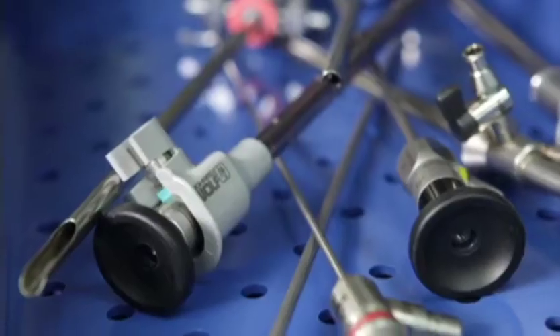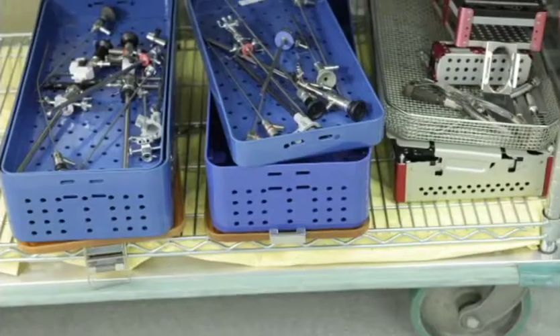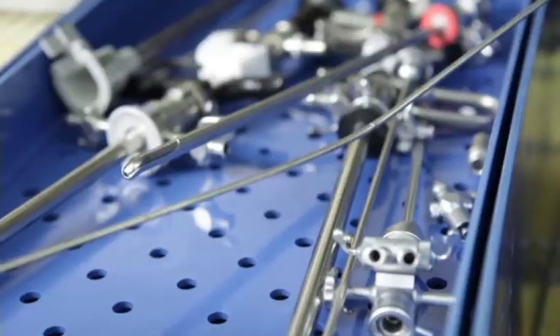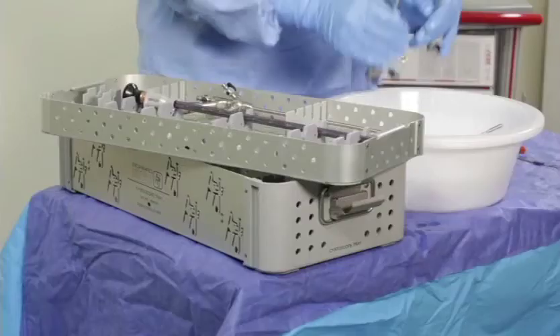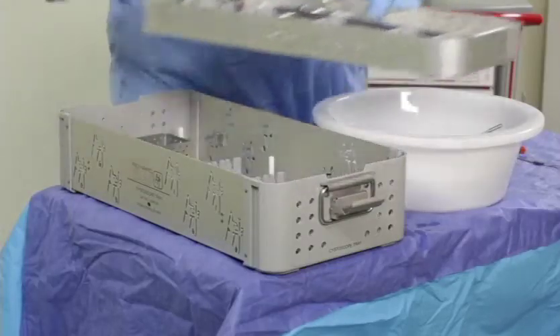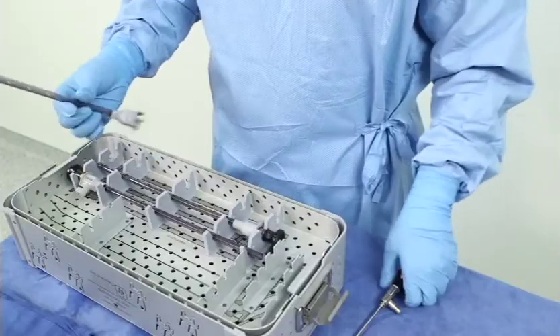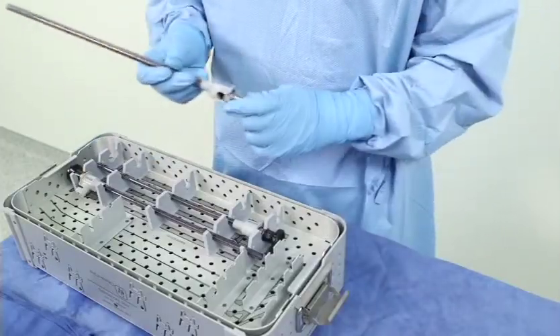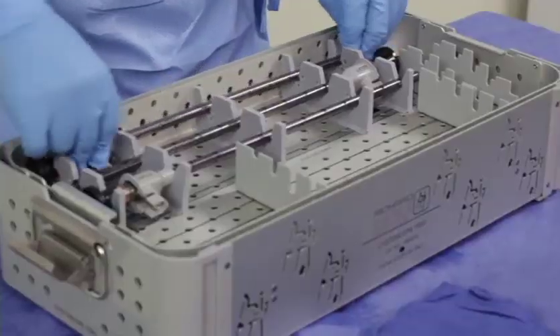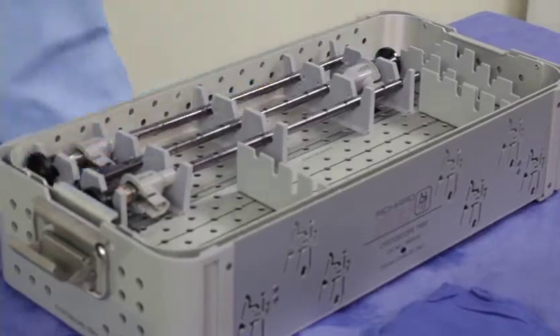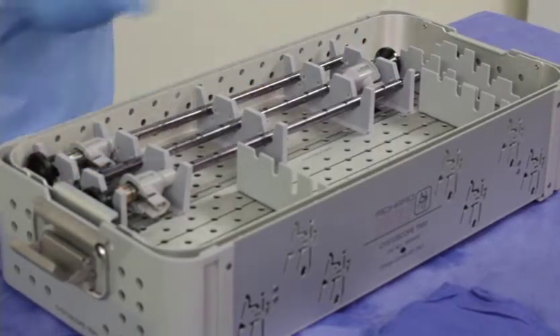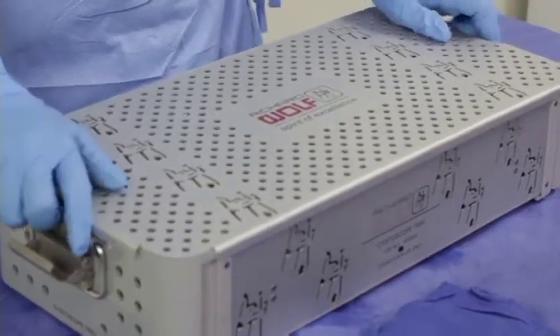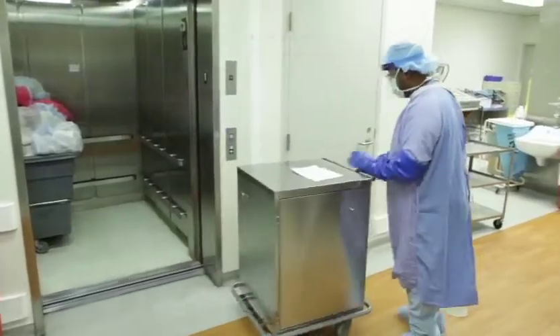Rigid endoscopes are very vulnerable during transport and can be commingled with other instruments that are heavier and could damage the scope during transport. Separate the endoscope from other instruments before transport. Place a Richard Wolf scope protector onto the endoscope as appropriate. Contain the endoscope in a tray by itself or in a separate transport bin from the other instruments. The rigid endoscope is now ready to transport to CSSD.